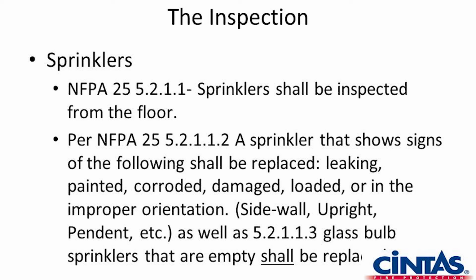About the inspection, we're talking about items in Chapter 5. Sprinklers shall be inspected from the floor. A sprinkler that shows signs of the following shall be replaced. If we see a leak from the sprinkler itself, and determine that the leak is not from a fitting above the sprinkler but from the sprinkler head itself, then that's cause for replacing the sprinkler. Also painted, corroded, damaged, loaded, or in improper orientation.